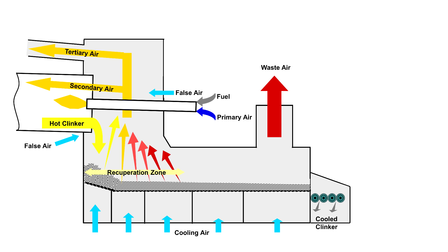There are two main zones in the cooler: the hot zone or recuperation zone, and the cold zone or after-cooling zone. There are two extraction points on opposite sides of the cooler. This creates a zero zone or mid zone in the cooler as seen with the dashed line.